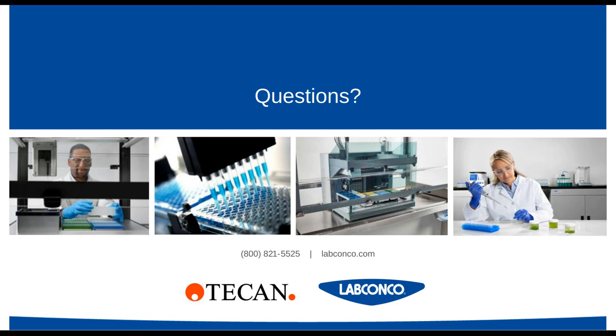Let's get started. Our first question is, do we need a biosafety enclosure for our COVID samples? We are running both Abbott ID Now and PCR assays. Great question. Yes, if the virus has not been inactivated prior to testing, it does need to be contained in a biosafety enclosure that provides personnel protection. So while that may be a Class I enclosure, oftentimes the sensitivity of those tests strongly warrants the use of a Class II Biosafety Cabinet.